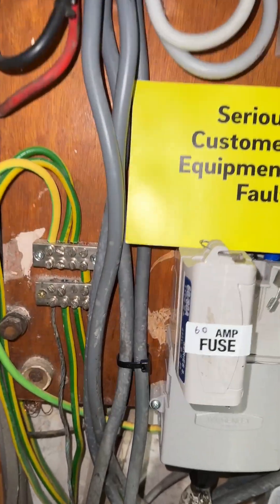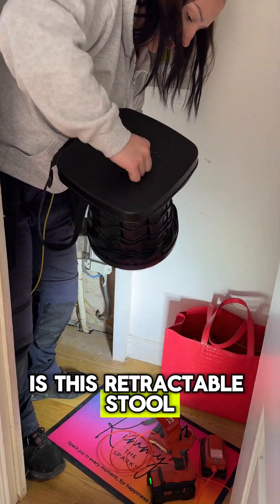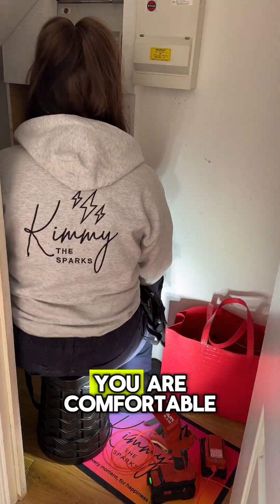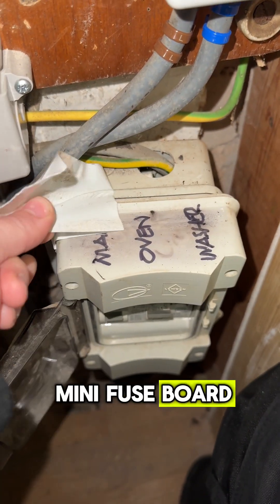The serious fault notice there is for the undersized meter tail. Also, a must-have for when you're doing fuse boards is this retractable stool because you can adjust the height to make sure that you are comfortable.